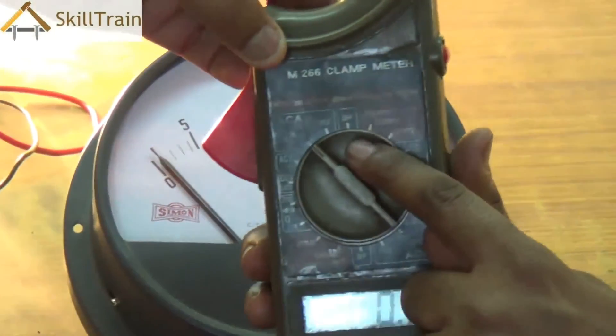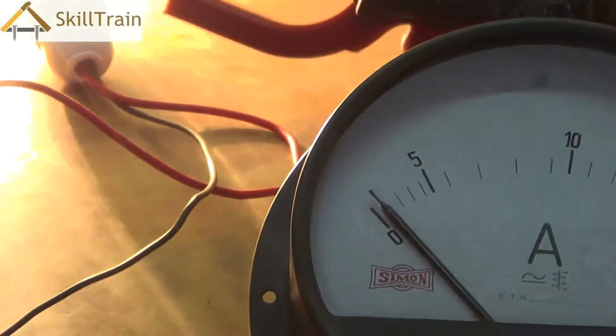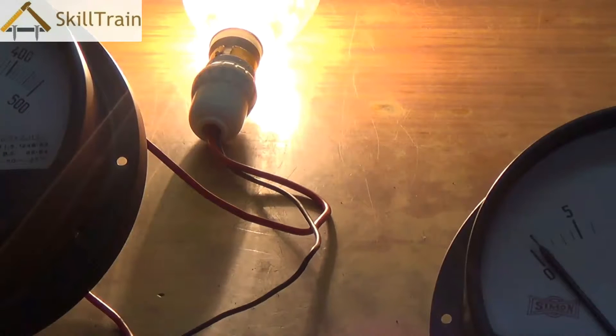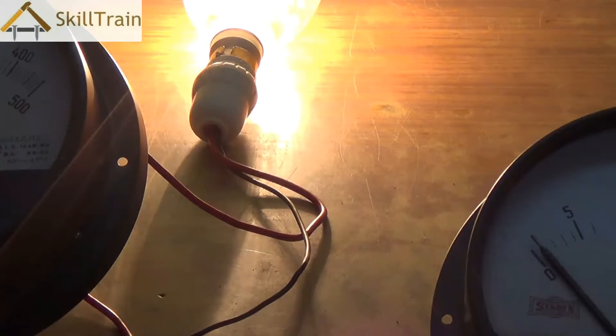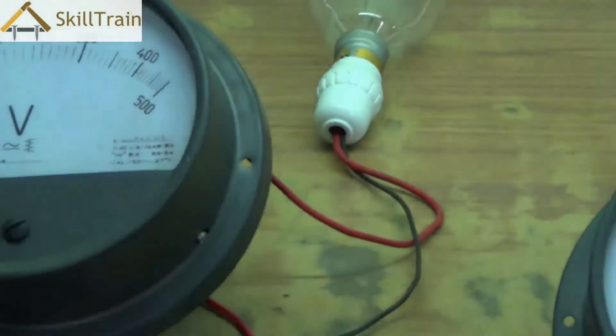You can also measure this current using a digital clamp meter or tong tester. Set the knob to the ampere 200 position, then clamp it around the phase or neutral line. You can see it digitally gives a 0.6-ampere reading. The clamp meter or tong tester gives a much sharper reading compared to the analog ammeter. Digital tools are widely available today and are far easier to use because they do not require you to connect any wires to specific components.